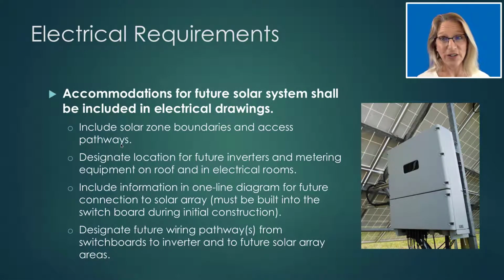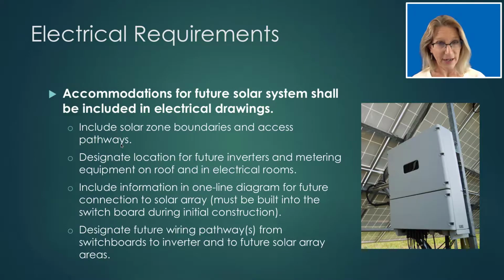Now, the electrical engineer or contractor, they are also required to include accommodations in their design for a future solar array in their electrical drawings. So in their documents, they need to include the solar zone boundaries and the access pathways. So the same information that would be found in the architectural drawings. They need to designate a location for future inverters and metering equipment on the roof and within the electrical rooms. And they shall also include information in their one-line diagrams for future connection to the solar array. And this really does need to be built into the switchboard during initial construction for the reasons we talked about earlier. And then they also need to designate future wiring pathways from the switchboards to the inverter and then to the future solar array areas.